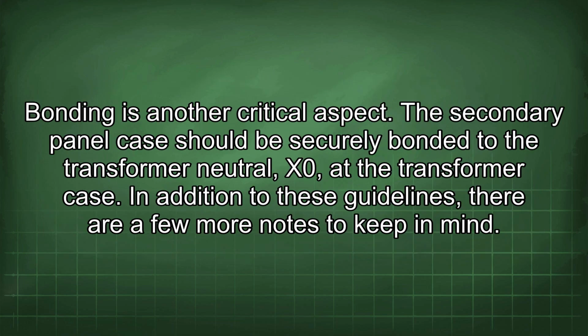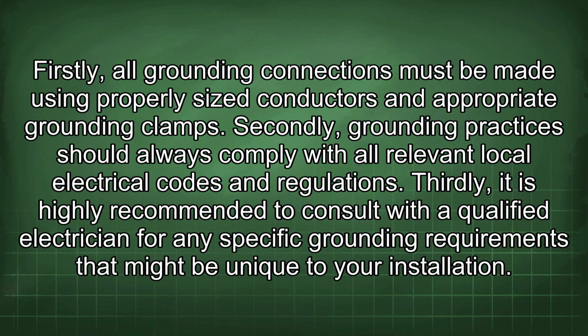Bonding is another critical aspect. The secondary panel case should be securely bonded to the transformer neutral, X0, at the transformer case. In addition to these guidelines, there are a few more notes to keep in mind. Firstly, all grounding connections must be made using properly sized conductors and appropriate grounding clamps. Secondly, grounding practices should always comply with all relevant local electrical codes and regulations. Thirdly, it is highly recommended to consult with a qualified electrician for any specific grounding requirements that might be unique to your installation.